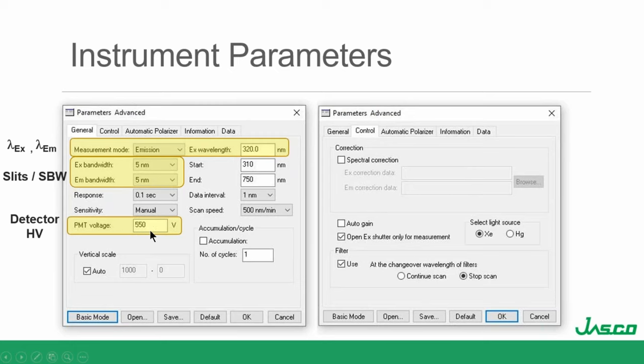Working between spectral bandwidth and detector voltages can give you a nice compromise of resolution and ample sensitivity. Remember the photomultiplier tube — if we adjust that voltage, we can increase the signal. Unfortunately, what else increases when I adjust the voltage? Noise. So that's why it's a trade-off. Also important, because all monochromators output other orders of light, would be an internal filter set — you can turn them on or off to get rid of second order scatter contributions.